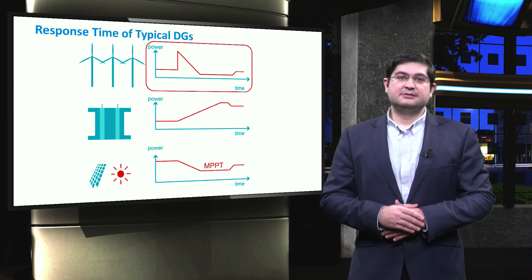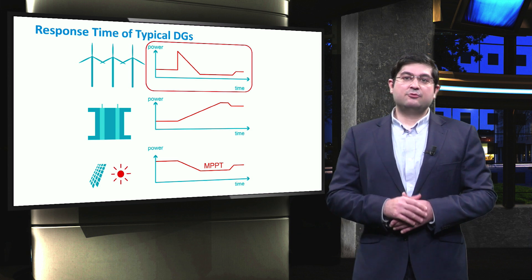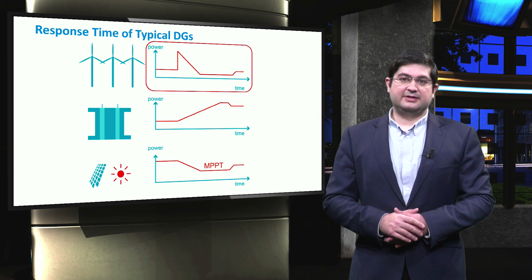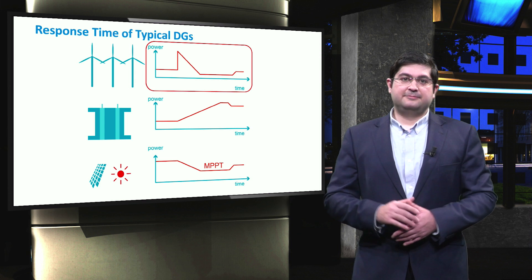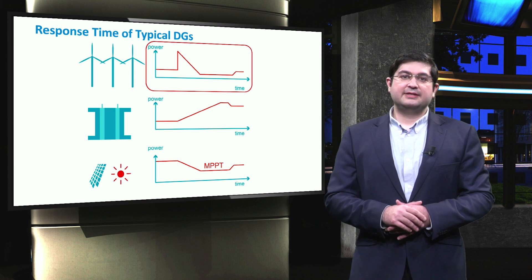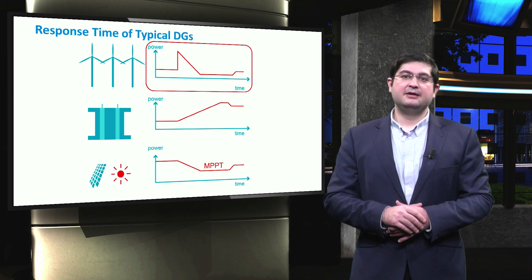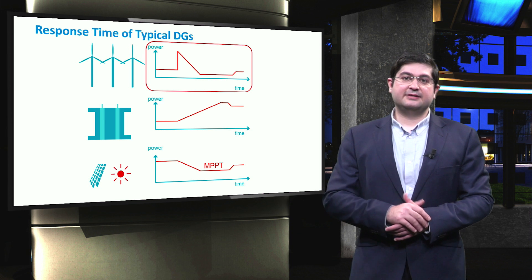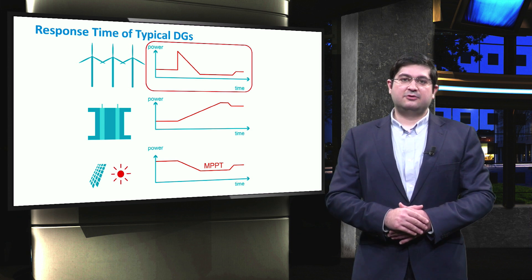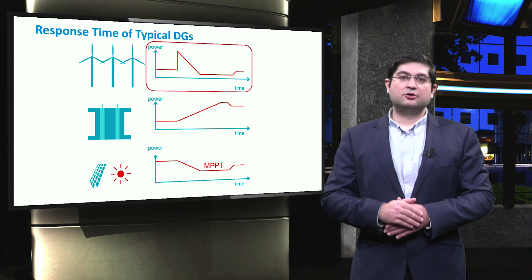In general, variable speed wind turbines are able to vary their active power very quickly following the frequency disturbance thanks to their power converters. However, as the rotor speed dramatically drops, they have to reduce their power support after a certain period of time, typically after tens of seconds depending on the inertia of rotor mass. Therefore, wind turbines can support the frequency only for a short period of time.